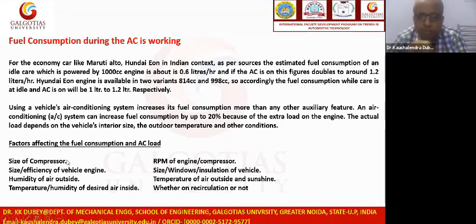So the size of the compressor matters, because the pressure is required after the compression, on the condenser side. As per the compression ratio, the main input factor for the compressor selection, compression ratio is a very important factor, and it also depends on which type of refrigerant is used. Like with R134A the compressor will be different, or if R22 is used the compressor will be different, because the thermodynamic property of the refrigerant is a very essential parameter for the selection of the unit.